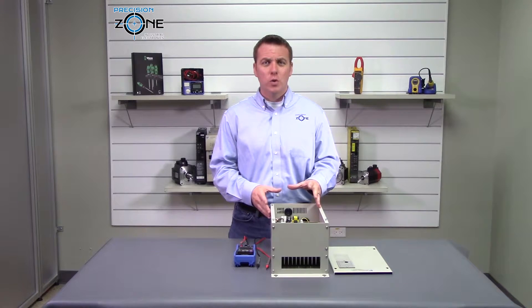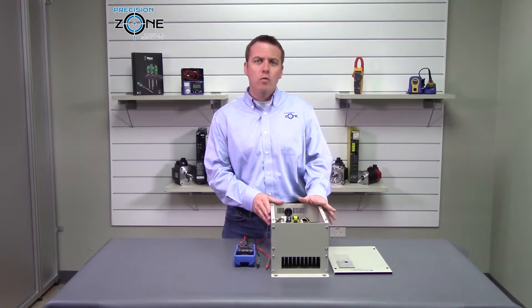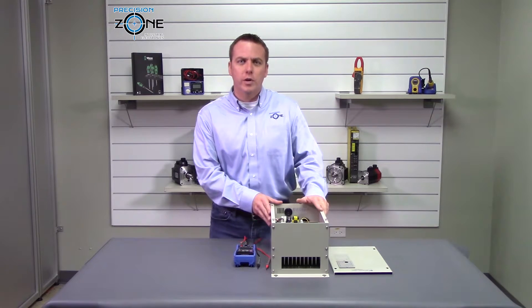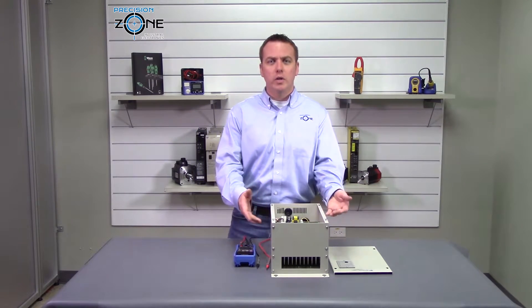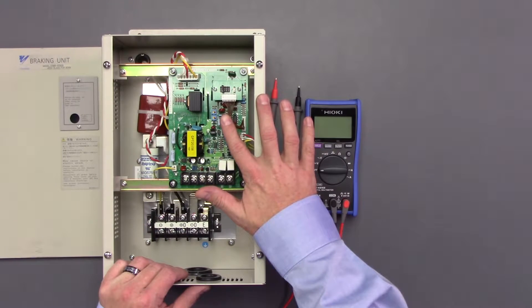There are no alarms on this unit, but one sign that you may have a problem is that you can be getting an overvoltage alarm on your inverter, and also while the motor is decelerating you're not seeing that LED light coming on.